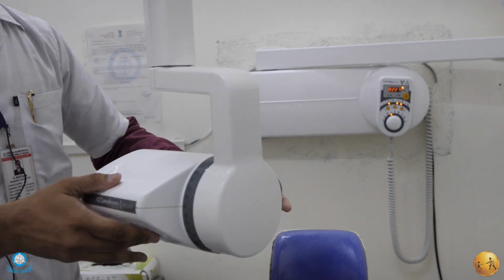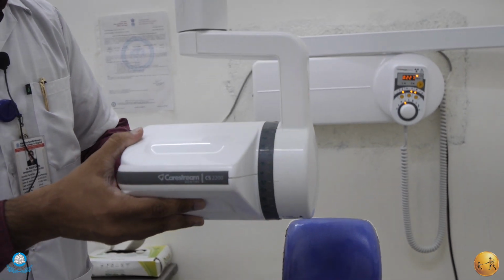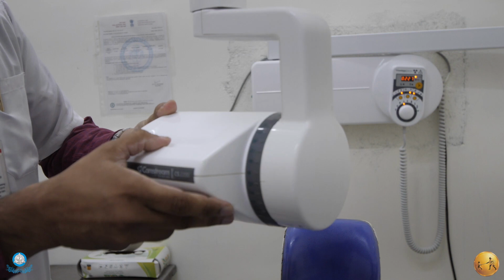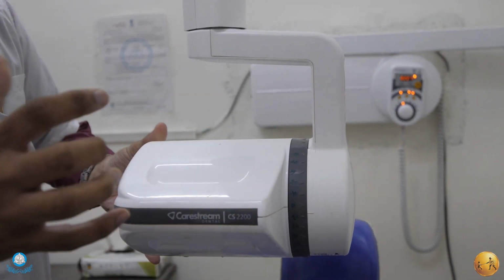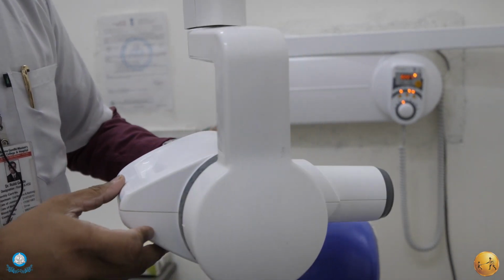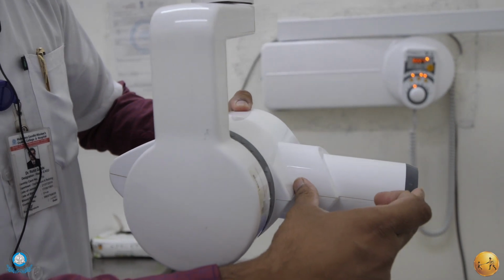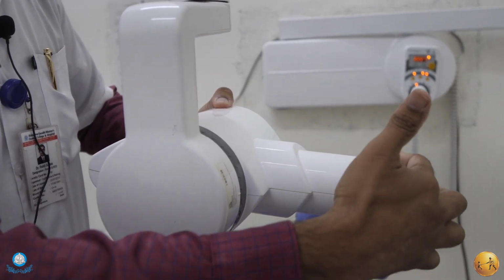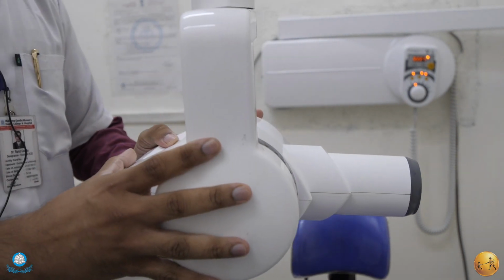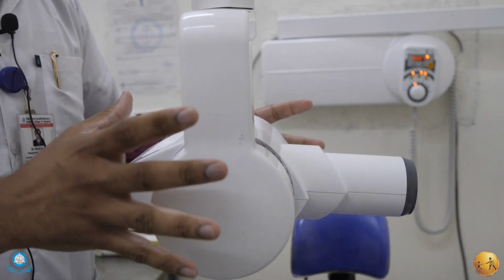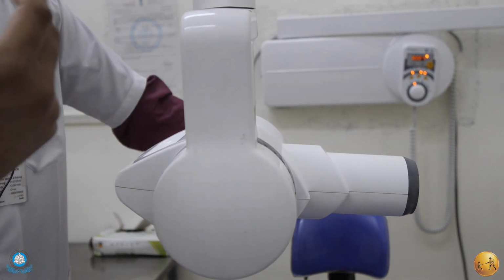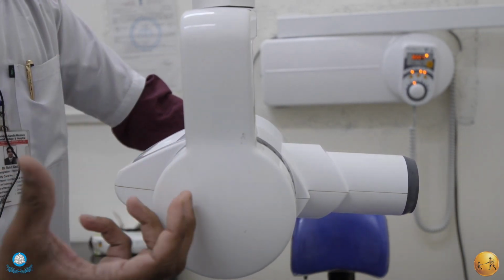Now coming to third part of X-ray machine, that is X-ray tube head. Now this X-ray tube head consists of position indicating device, which is in form of small cylinder, and tube head itself. Generally this tube head is heavy metal housing which contains X-ray tube, which is where actual X-rays are produced.